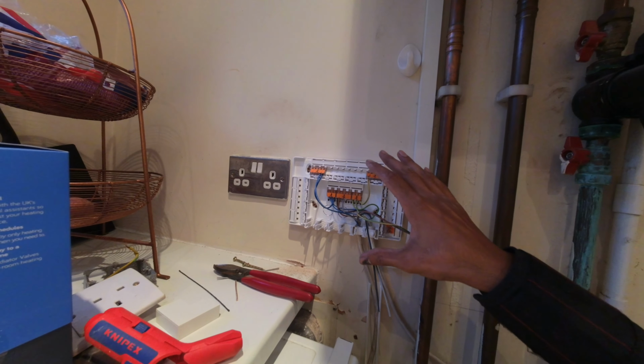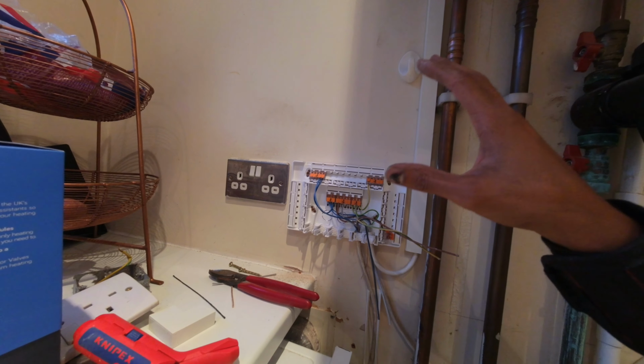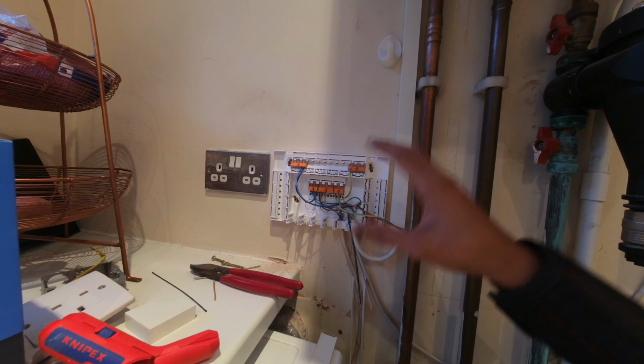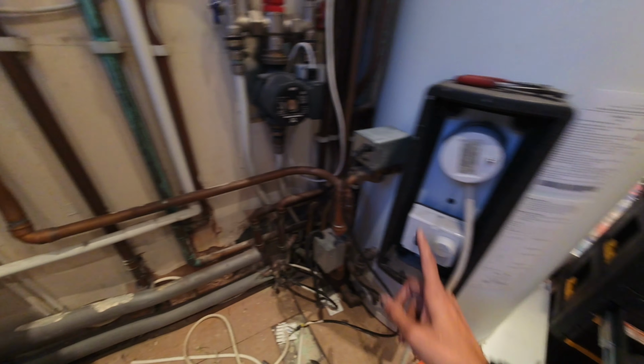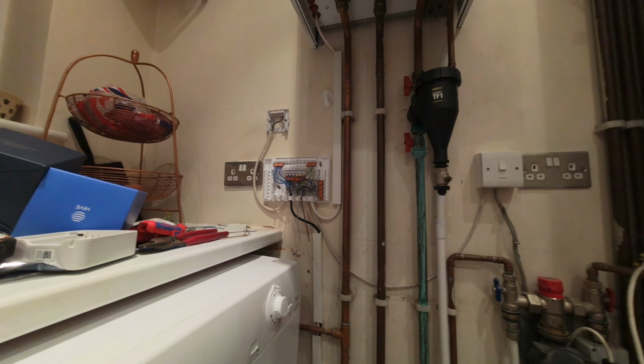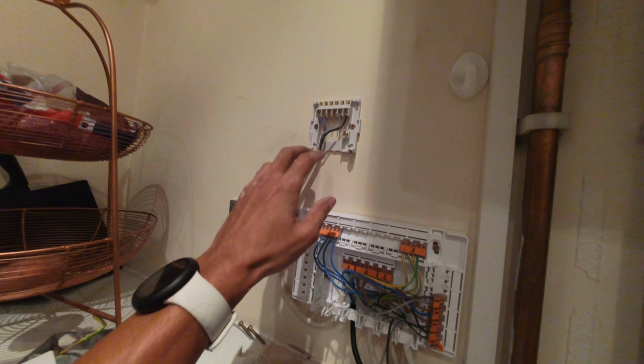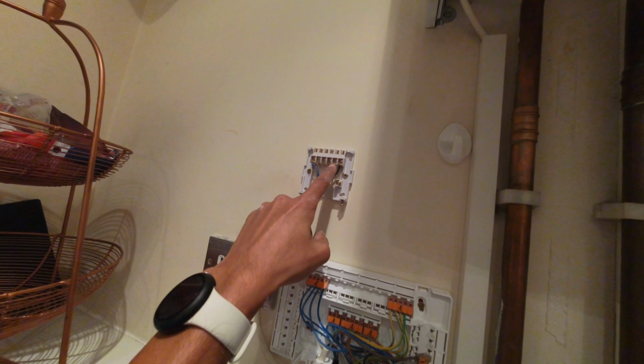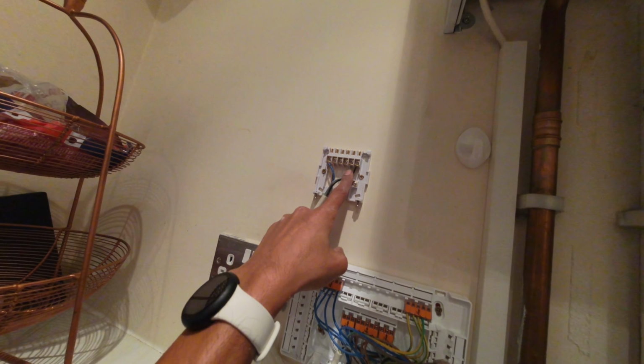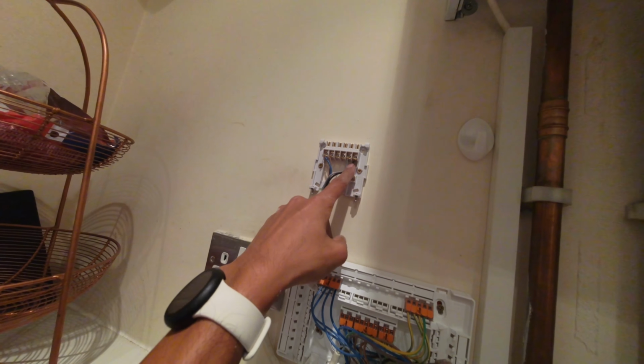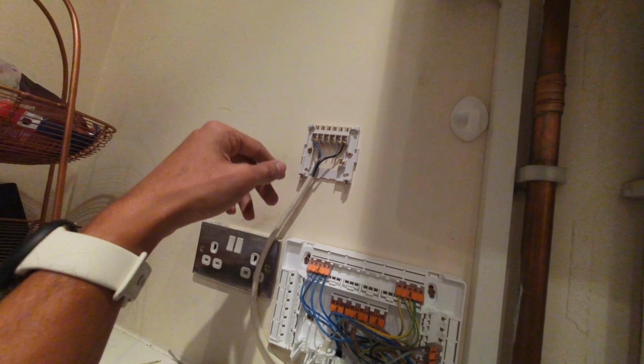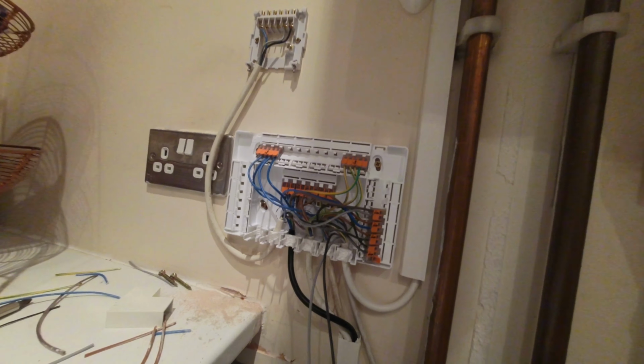So started in the heating zone valve, I'm going to finish wiring that up, then I'm going to do the same with the hot water zone valve, and I also need to run another cable here to the cylinder stat as well. Okay, wiring is pretty much all done. So I've mounted the Hive backplate there. It's a twin channel Hive, so I've used grey in number 3 for hot water, black in number 4 for heating, live and neutral, live and neutral. So they come down into here.